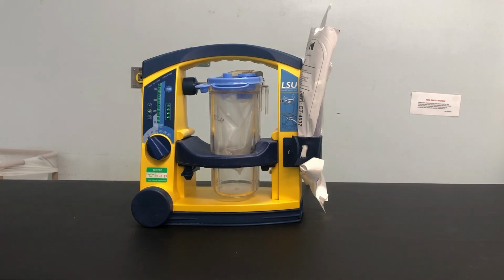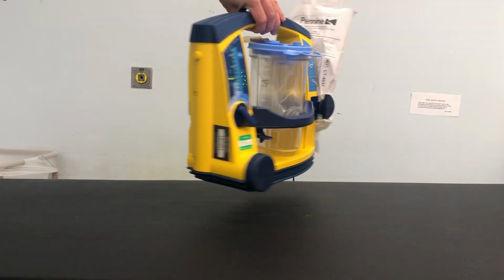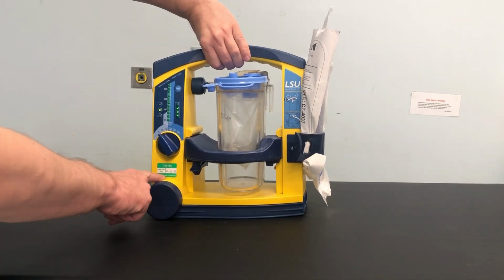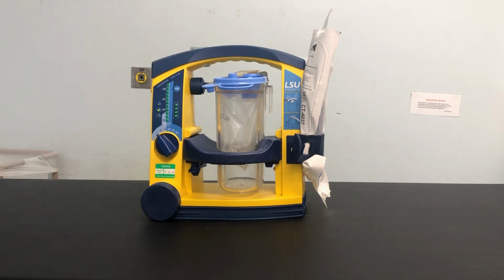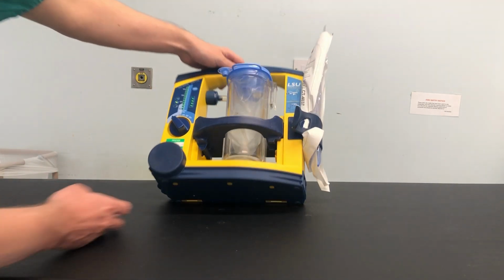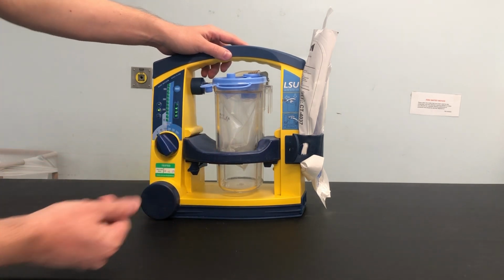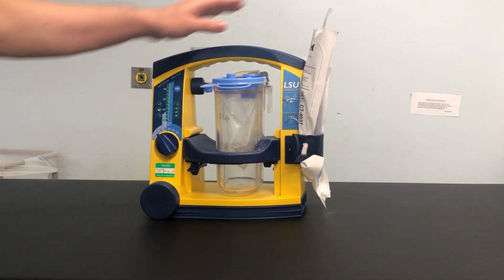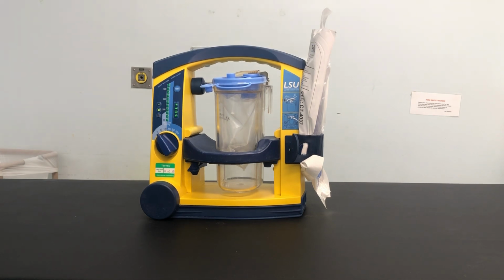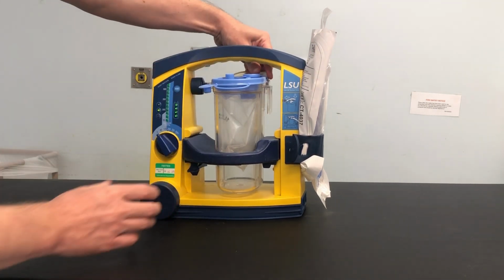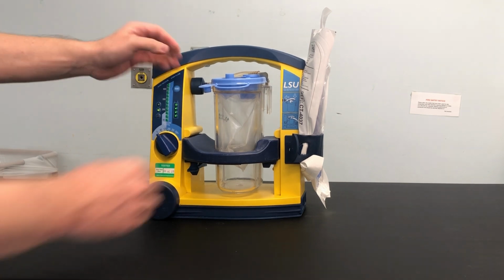The LSU should only be used by staff who have been trained and assessed as competent as per the NUH Medical Devices Training Policy. So initially, when you get your device, you want to check the device for the presence of the NUH Equipment Library item number sticker and service sticker indicating the device is within its service period. Visually inspect the device for any obvious signs of damage and or dirt, and ensure that no parts are missing, and ensure that all accessories are available. Ensure that the vacuum connector tubing is properly connected to the LSU and to the canister, and check that the lid of the canister is properly sealed by completing the following.